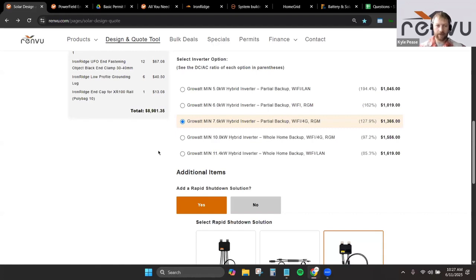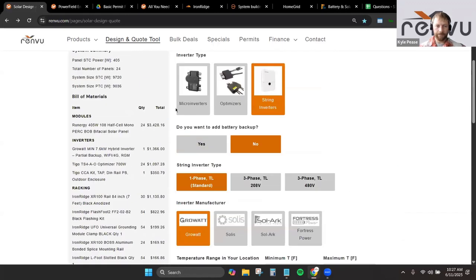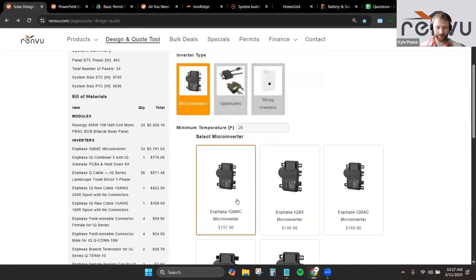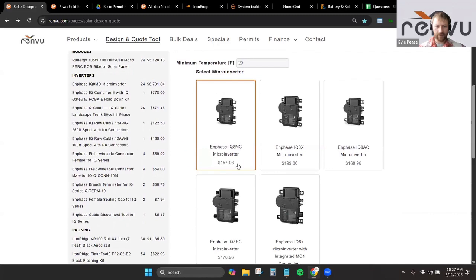Some people really like the microinverter option and prefer running AC up there, so then you can swap over to microinverters. IQ8 MCs, 24 of those, each of those is 320 watts of max continuous. So if we have 320 times 24, that's 7.68. So that's a fully loaded solar backfeed breaker with a 200 amp main panel and a 200 amp main breaker. Really common residential system there.